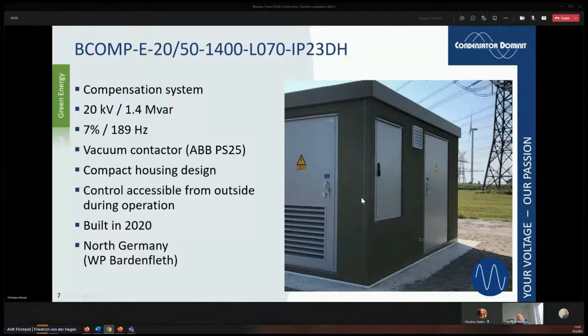Another solution we provide specifically for the renewable energy market is a very interesting phenomenon we have in solar parks, also in wind parks, but mainly in solar parks. You have huge cable distances, and with these cables you have a transformer. The cable is a capacity, the transformer is an inductivity, and that creates a grid resonance. And that very often leads to serious trouble, because as soon as the energy reaches a certain point, the grid resonance causes the whole solar park to trip.